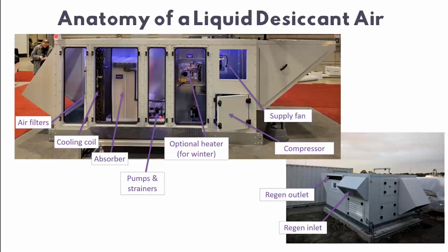Additionally, protecting the desiccant system is a pair of T-strainers. As long as you have at least 3 fingers and a thumb in one hand, it's something that is unscrewable. You rinse it out, you put it back in. That is the only maintenance on the desiccant system itself. Outside of that, I'll talk about maintenance a little bit later in the presentation.